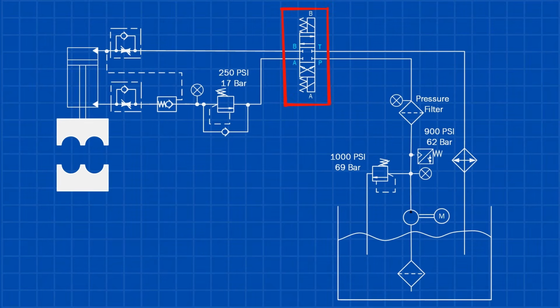If the fuse isn't blown and the output card is fine, there's a less common issue to consider. Sometimes, if the hydraulic oil is contaminated or dirty, the spool inside the valve can get stuck in the center position and fail to move. In this case, you'll need to replace the valve and replace the hydraulic oil and the filters.